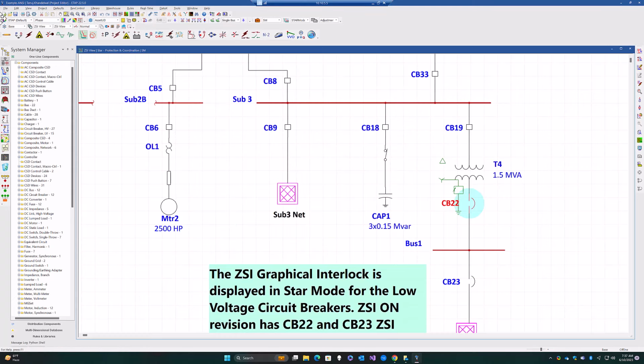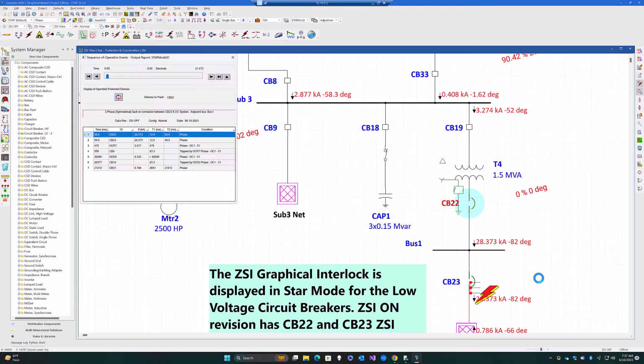So what we'll do is we'll just switch over to ZSI off, and I just want to show one point here in terms of the purpose of the ZSI. So here we can see that we have CB22 and 23 both tripping at the same time if you have a fault downstream of circuit breaker 23. And this basically means we don't have good selectivity on bus 1.